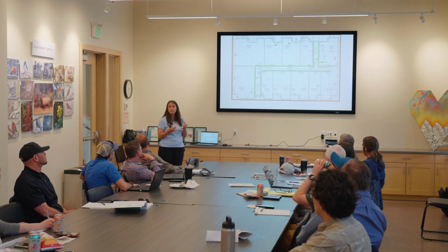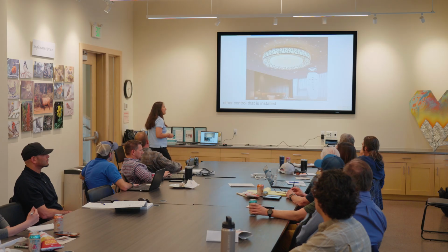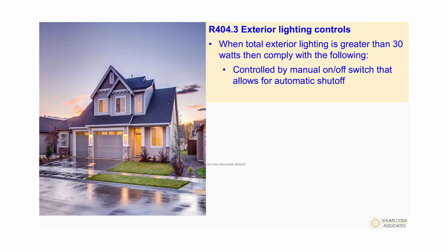Because on the commercial side for corridors, they don't reduce down to 0, right? They don't just shut off. It reduces by 50%. This doesn't have any of that same criteria. It's just that this is what it has to have, one of those things. So we want to make sure that we have that there. Those lights have to see that. Unless they fall under commercial, then commercial corridors, other than stairs. Stairs in the 21 are still exempted out of that criteria.